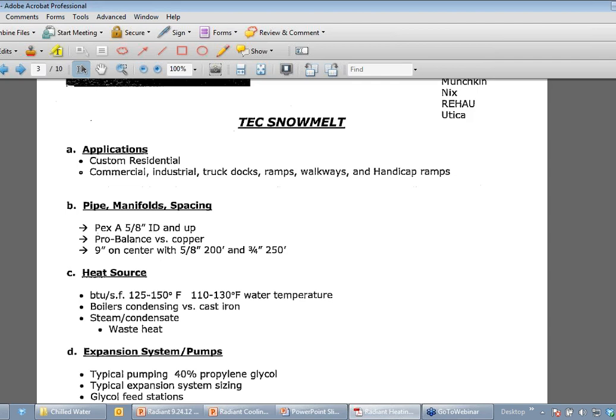Here you go. Here's on the high end, 110, 120, 130 degrees, like a radiant system would be. But as long as it's above 50 degrees, you're probably going to be able to melt snow. So don't look at this cheat sheet here and say that I have to have 120 degree water to melt snow. If you have some other source of free energy, like condensate coming off a cooling system in the wintertime, and that condensate is 80 degrees or something like that, I don't know, maybe off a cooling system. You could use other sources of energy to do some of that snow melting if you need to. You'll need a higher flow rate.